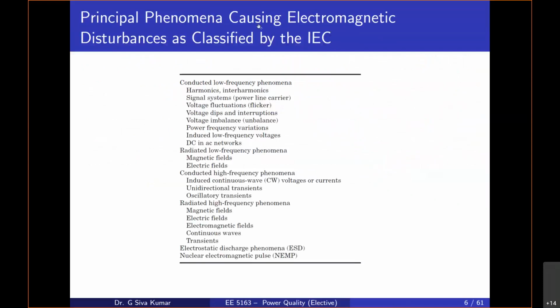The principal phenomena causing electromagnetic disturbances, as classified by the IEC: for low frequency phenomena, they are categorized into harmonics, interharmonics, signaling systems, power line carrier, voltage fluctuations, voltage dips and interruptions, voltage imbalance, power frequency variations, induced low frequency voltages, and DC in AC networks. This is with respect to conducted low frequency phenomena.